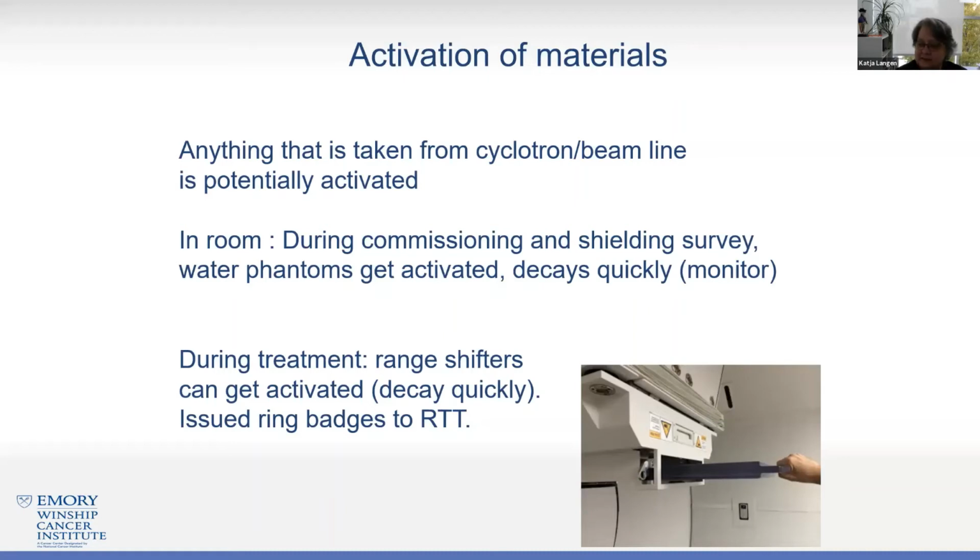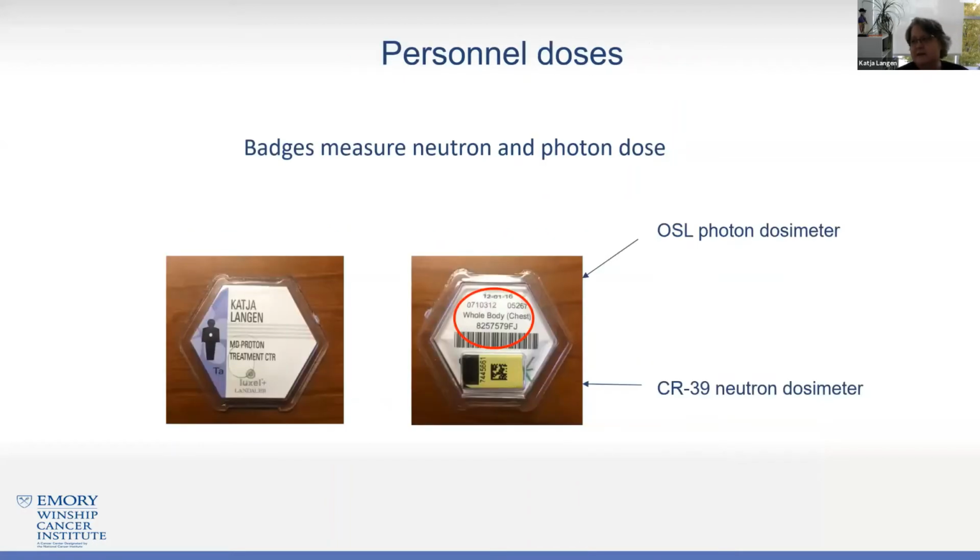So we wanted to make sure our radiation therapists didn't pick up any extremity dose. So we issued ring badges to our therapy team, and it turns out we stopped doing this at some point because we did not get any readings on them.